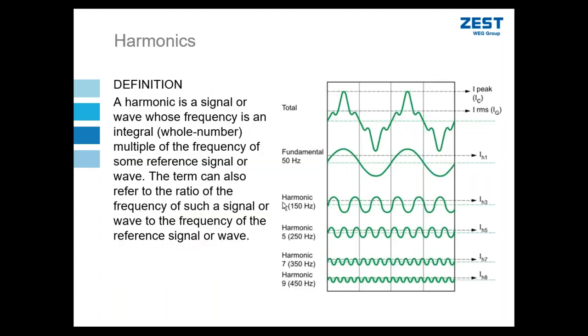All right, so we've shown some distorted waveforms. Now as engineers, we want to analyze those waveforms and be able to compare them to something. So the way we do that is by breaking up a distorted waveform into a series of harmonics. And so in this diagram, you can see our final waveform is quite distorted, and it's very difficult to make sense of this waveform or to compare it to some standard or compare it to other waveforms for that matter. So what we do through Fourier analysis is we break this waveform up into a fundamental sine wave and then a series of harmonic integers added to that fundamental, which ultimately will give me this distorted waveform. So we can vary the amplitude of each of these harmonics in order to change what the distorted waveform looks like.